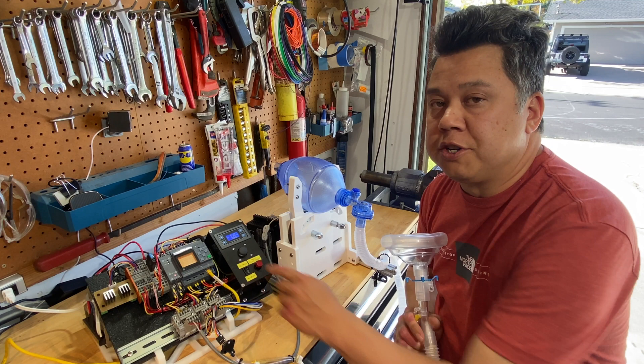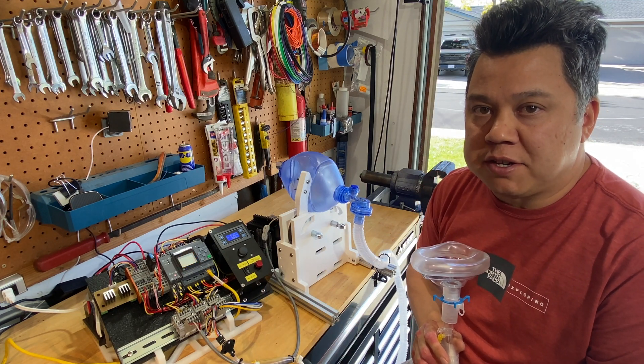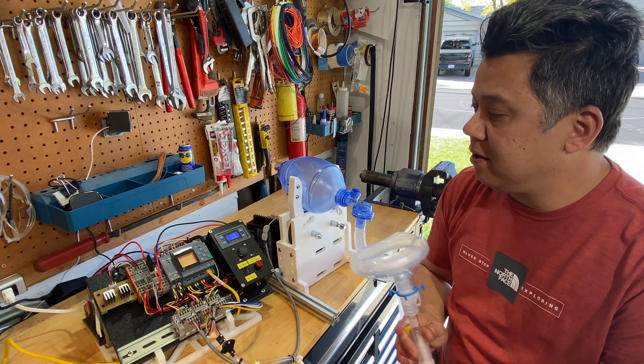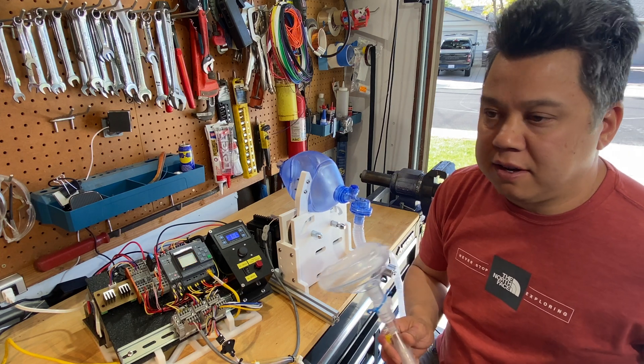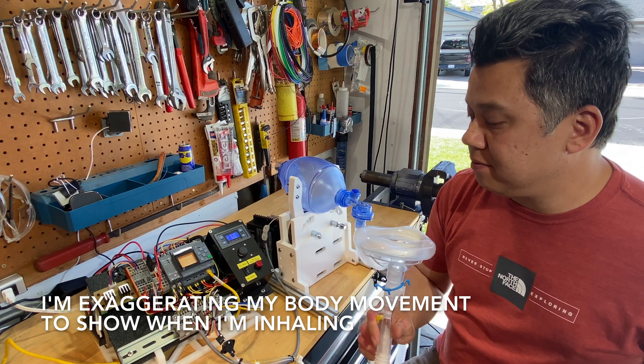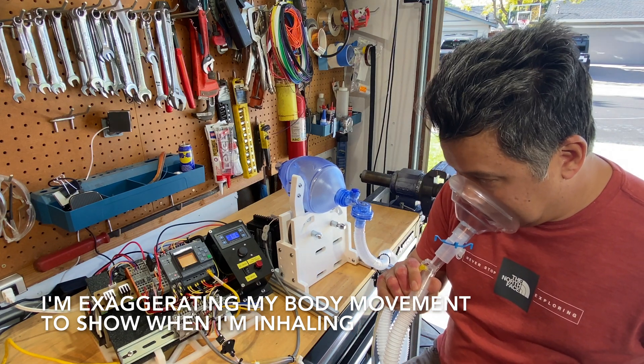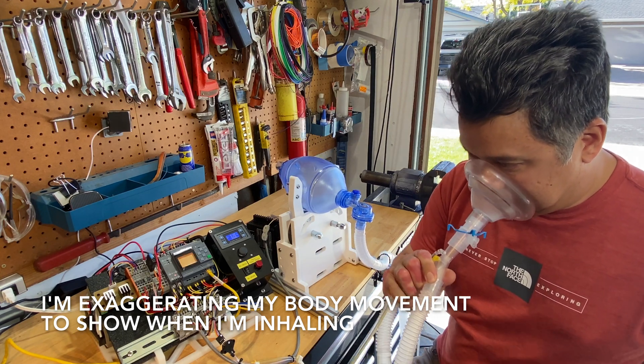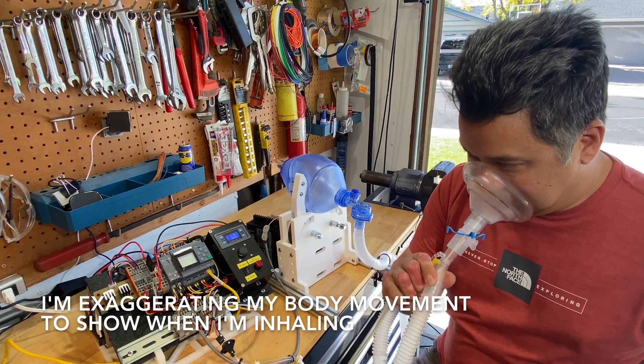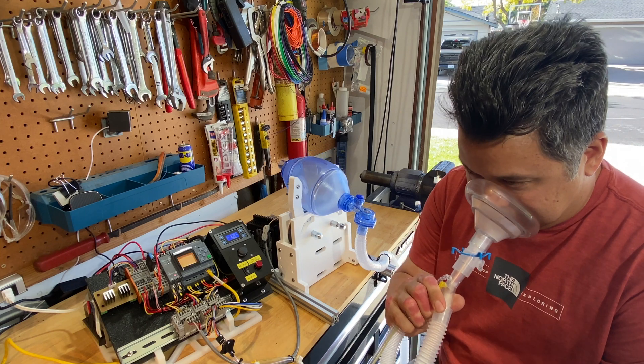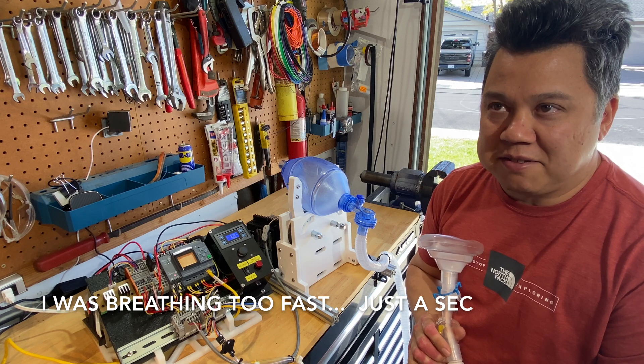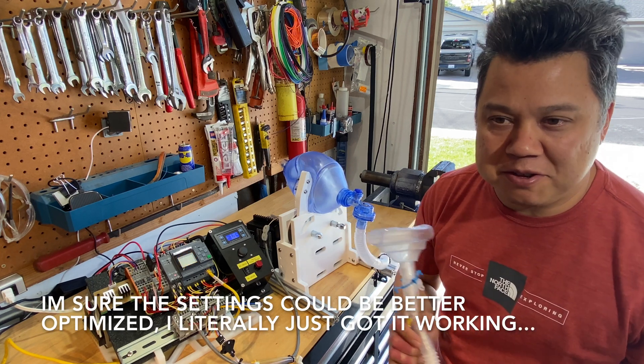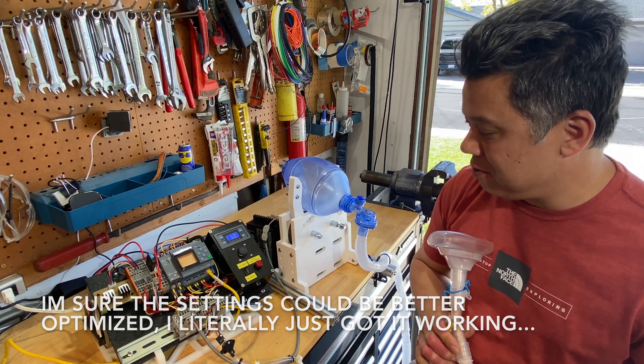So this one always stays in sync and I can show you how it does that. The screen turns orange when it's in a wait state waiting for the patient to inhale. If the patient takes too long or the inhale is not sensed, it will force a breath after a few seconds and it's all configurable on the screen. So I'll show you now how the breath sensing works. The sensation is a bit like breathing through a scuba regulator. I've never used a ventilator before so it's kind of a new experience for me.